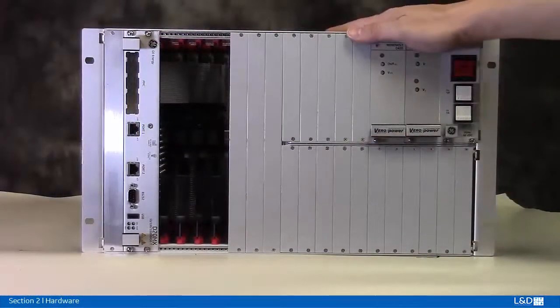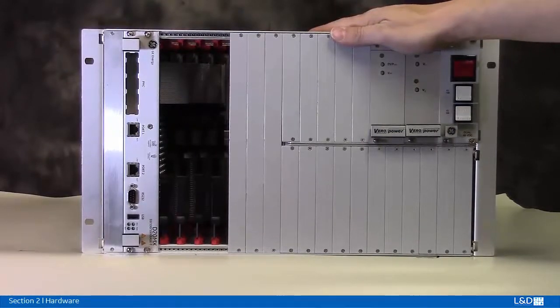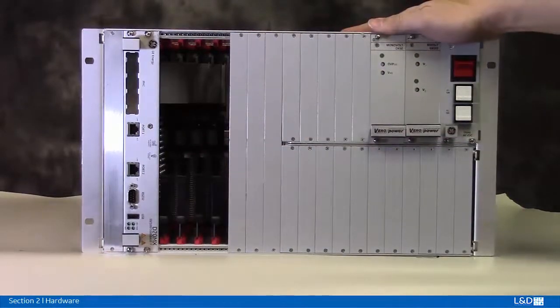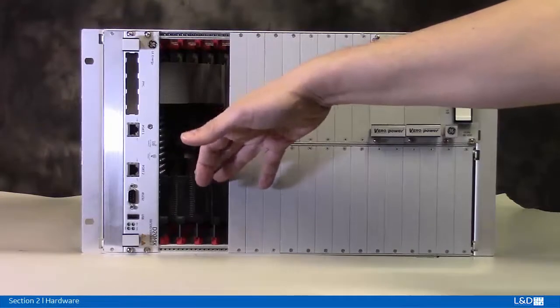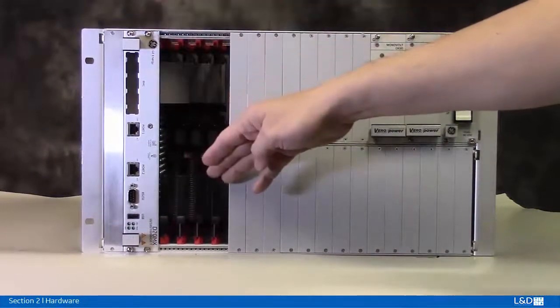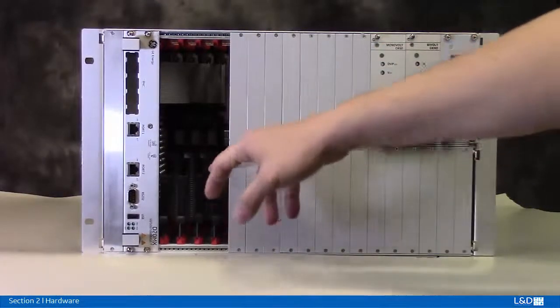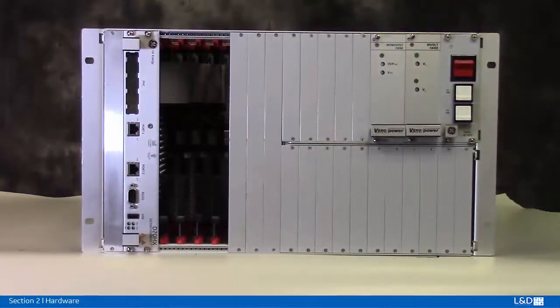For a vertical D20 MX, the chassis, of course, is bigger in order to accommodate the extra serial expansion cards. This one was equipped with 4 extra expansion cards, in addition to the main card. Like we said in the previous demonstration, it's 7 ports per card. When you've got 4 cards and the main, that's a total of 5 by 7, 35 serial ports.